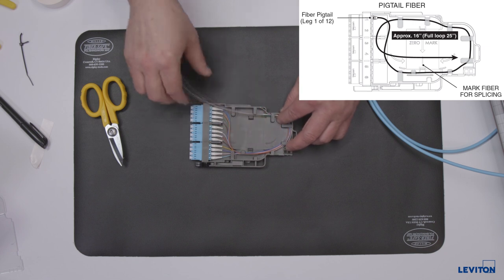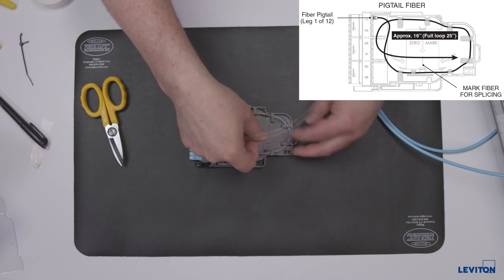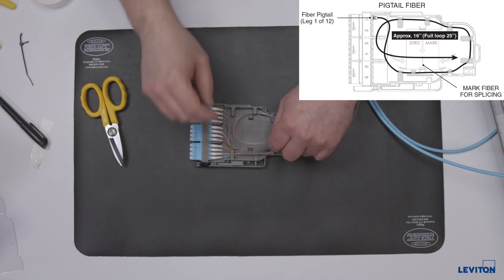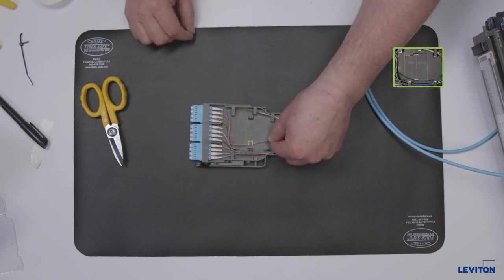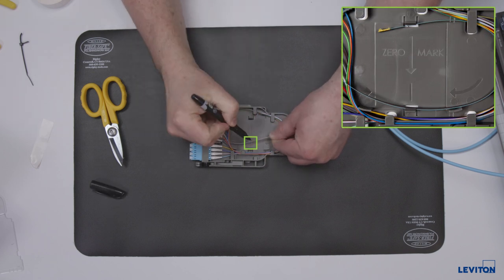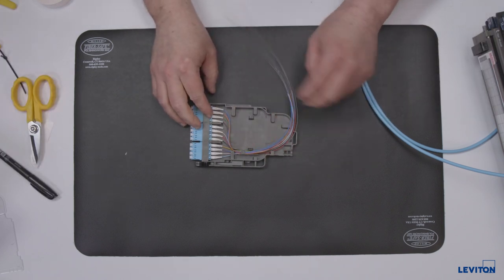Route the pigtail counterclockwise through the management tabs until all the slack is stored, one full loop, and the fibers are entering the splice sleeve holder area. Mark the fibers at the zero mark guide and remove all fibers from the storage area.